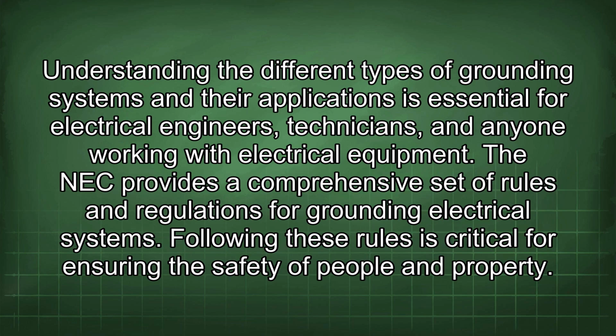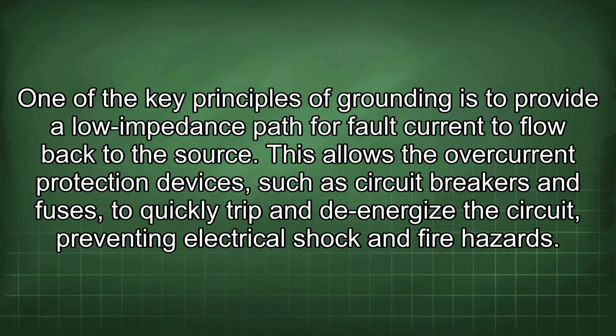electrical equipment. The NEC provides a comprehensive set of rules and regulations for grounding electrical systems. Following these rules is critical for ensuring the safety of people and property. One of the key principles of grounding is to provide a low impedance path for fault current to flow back to the source. This allows the overcurrent protection devices, such as circuit breakers and fuses, to quickly trip and de-energize the circuit, preventing electrical shock and fire hazards.